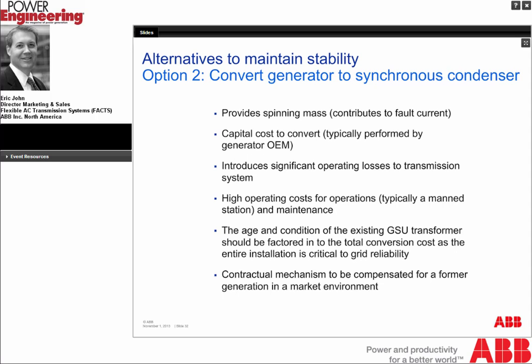The last point to be made about the conversion is a commercial one, and that is in many ISO or RTO type environments, there's no straightforward mechanism to take a generator which sits in an unregulated pool of assets, if you will, and convert that to a transmission asset and earn a return under the tariff. And I know that there is talk within FERC and at the ISO and RTO level to compensate for reactive support, but there's not necessarily a contractual mechanism to be compensated for taking this former generation asset and converting it to a transmission one.